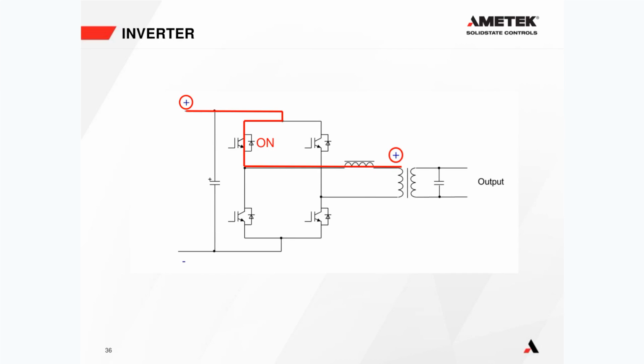So the same example for the charger I'm going to do for the inverter. Remember, we have our positive over here, and that's usually going to be connected to our battery back here. And if we only turn this IGBT on, yes, we will get that battery voltage and we will have positive on this side of the transformer. But because we don't have a return path to the negative, we get nothing on the output here. With only one IGBT on, nothing happens.